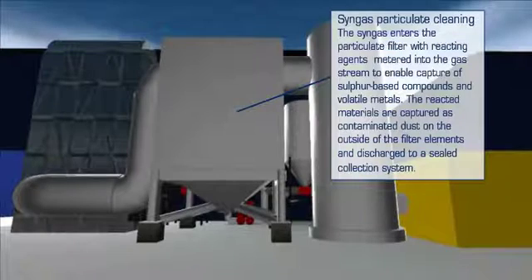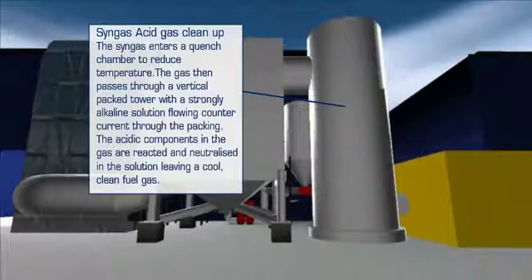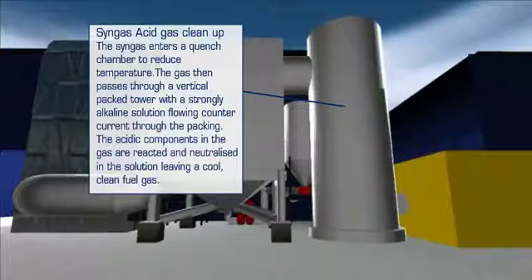The syngas flows to the particulate filter where a reacting agent is metered into the gas stream to enable capture of sulfur based compounds. The reacted powder coats the filter and traps contaminated dust, allowing the gas to pass through. The syngas then passes through a vertical packed tower containing a strongly alkaline solution. The acidic components react and are neutralized in the solution, leaving a cooled, clean fuel gas suitable for use in a gas engine.